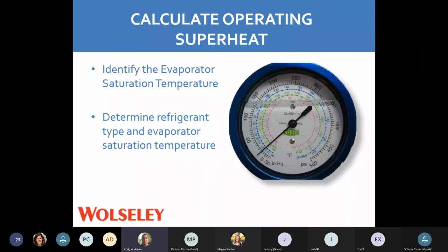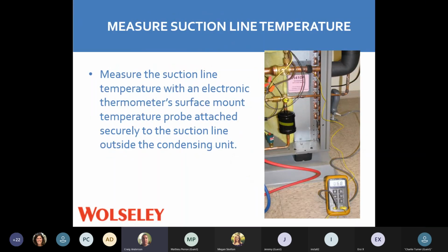So calculating operating superheat. Identify the evaporator saturation temperature, determine the refrigerant type that you're using, and the saturation temperature. So on your gauges, on your low side, you'll have the pressure that's on the outside, which is your PSI. And then inside your gauges will tell you the different freons, whatever you're working on that day, will tell you saturation temperature. So measure the suction line temperature with an electronic thermometer. Clamp on is always better. Hook it up to your meter, or if you have a special thermometer that will clamp onto the pipe. You could use a pocket thermometer to get you through, shove it through the insulation. We want to get a reading on that pipe. Clamp on gets a better firm fit on there. So attach it securely to the suction line outside of the condensing unit.